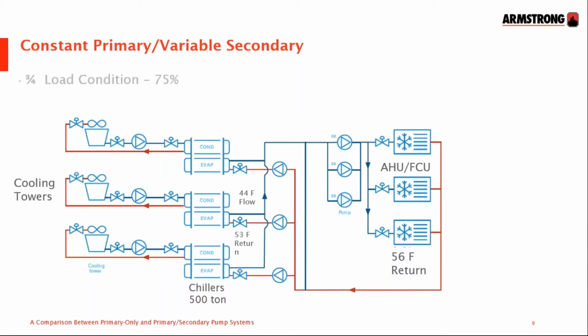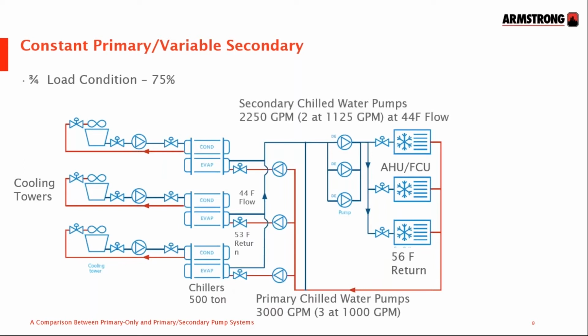Let's go to 75%, 3/4 load. We'll continue to have the 3 primary dedicated pumps pumping through the chillers at 1000 gallons a minute each. As the system now has a 75% load, we'll only be needing 3/4 of 3000, 2250, which will be divided between each of the 2 pumps at 1125 GPM. Control valves here will have throttled down on the flow because the building management system says they don't need so much cooling going into the rooms, into the zone served. The temperature will come back here at 56 degrees, maintaining a 12-degree delta T across these zones.